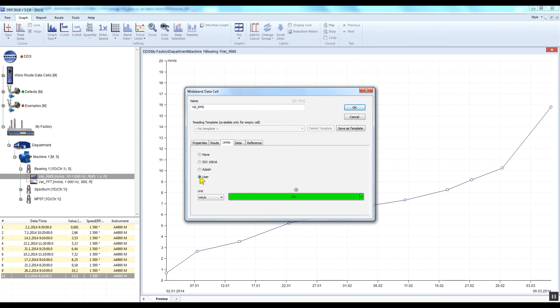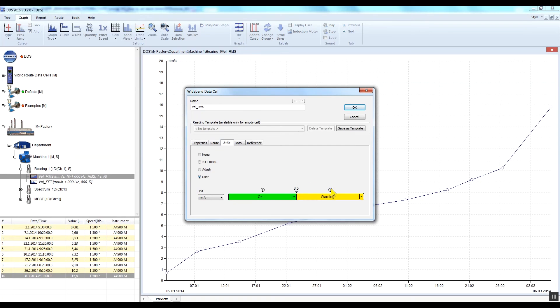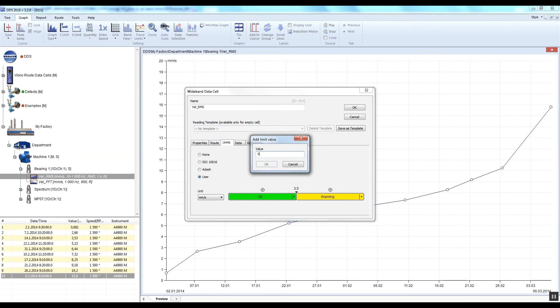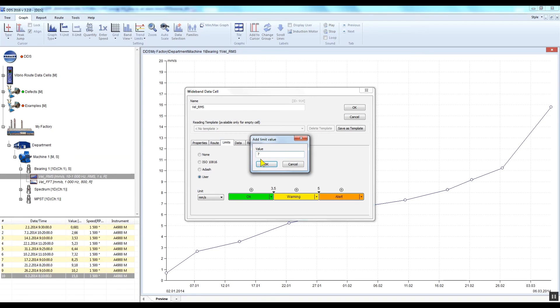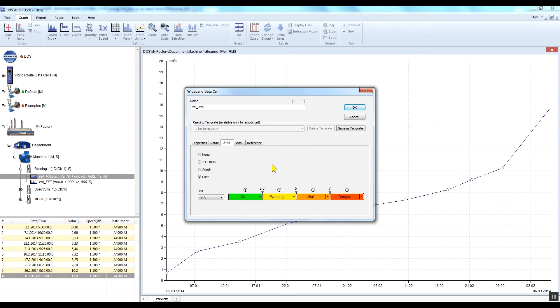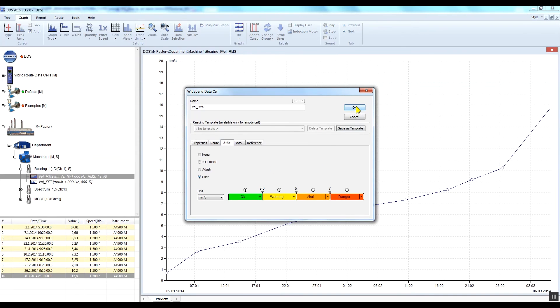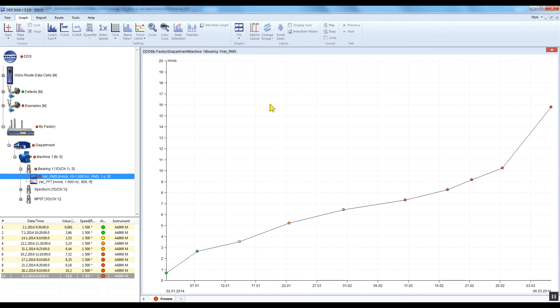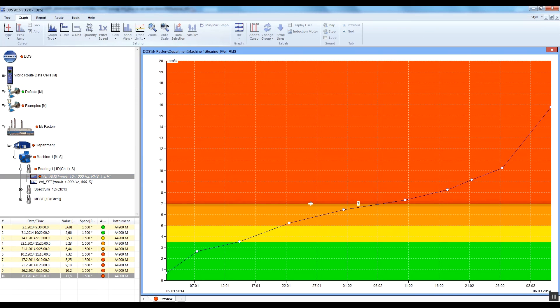Now select the User option. Click on the plus icon and enter the first value for the warning limit. Click on the second plus icon and enter the value for alert. Click on the third plus icon and enter the value for danger. Double-click on any limit value if you want to edit it. Confirm by clicking OK and your limits will be applied. If you change the limit appearance to lines or bars, you can edit alarm limits manually by holding the left mouse button on any alarm edge and moving the mouse.